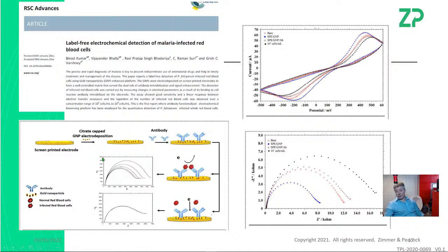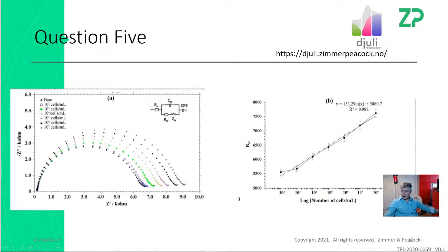They have used things like gold nanoparticles. There's nothing special about gold nanoparticles for me. They just increase the surface area to give you a higher signal density. But to the people who are reaching out to us regarding how to make a malaria sensor, or how we would do it, we would follow the principles in papers like this, but we would not use the gold. As I say, the gold price is going very high, and I think gold is an in-demand material. I really don't see it coming back down in price, so I would actually recommend something like the HyperValue carbon electrodes.